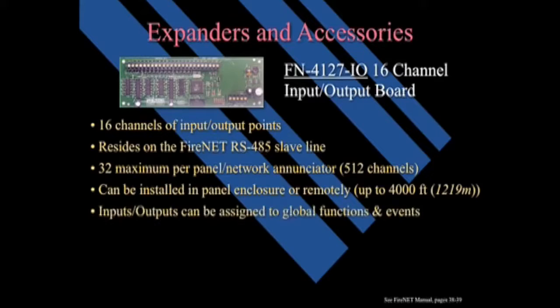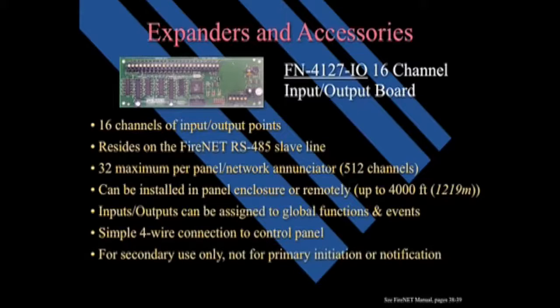The inputs and outputs are completely programmable and can be assigned to global functions and events. And the wiring is a simple 4-wire connection to the panel, 2 wires for the RS-485 comms, and 2 wires for auxiliary power. Since inputs and outputs are non-supervised, they are for secondary use only and not for primary initiation or notification. The most common application of the I/O board is for a LED graphic annunciator.